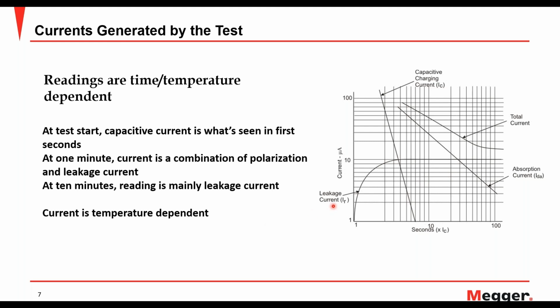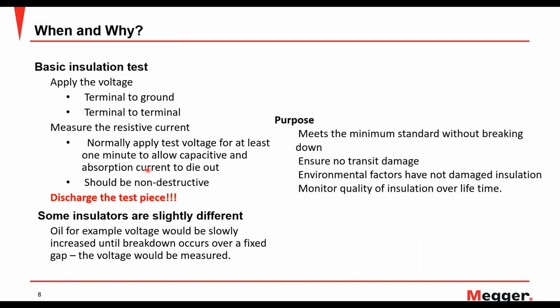And these readings that you get, whatever gigaohm or megaohm or any reading that you get, are time and temperature dependent. So time, we already discussed what combination you see in which part of time. Also, temperature plays a big role. Whenever you are measuring any type of resistance, it is always temperature dependent. So we need to account for that factor, and that's why most of the times we correct it to 20 degrees C or 25 degrees C depending on where you are, and that gives you comparable results. Because one day you're going to test at 15 and the other day it might be 25 or 27. So you need some comparison between the two, and we use correction factors to correct it to a specific temperature to make the results more comparable.